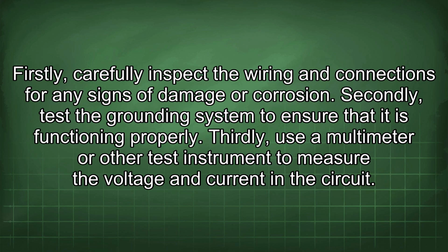Firstly, carefully inspect the wiring and connections for any signs of damage or corrosion. Secondly, test the grounding system to ensure that it is functioning properly. Thirdly, use a multimeter or other test instrument to measure the voltage and current in the circuit.